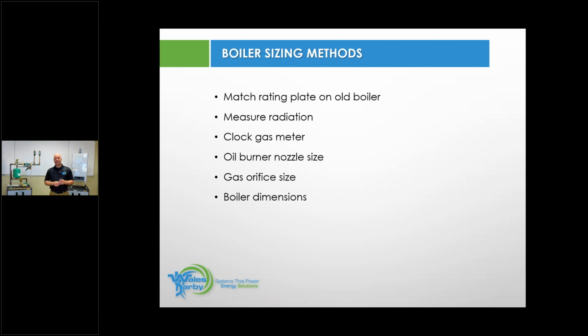If the boiler doesn't have a tag on it, you can look at that burner. Maybe the burner has a tag on it and it tells you what the input is. If you have absolutely nothing in the boiler room, okay, fine, we get it. It happens. Probably not a bad idea to go around and measure the radiation. That would be good. You can clock the gas meter, and that tells you how much gas the unit uses. Doesn't really give you the proper size.